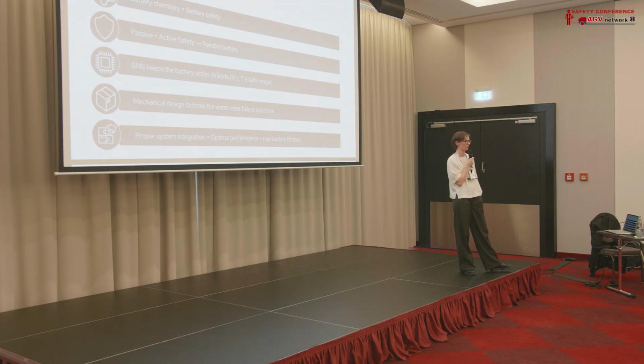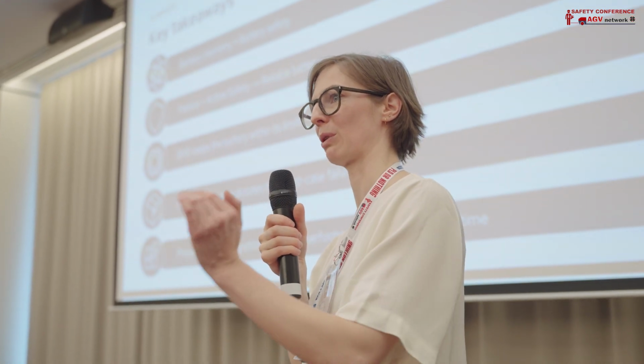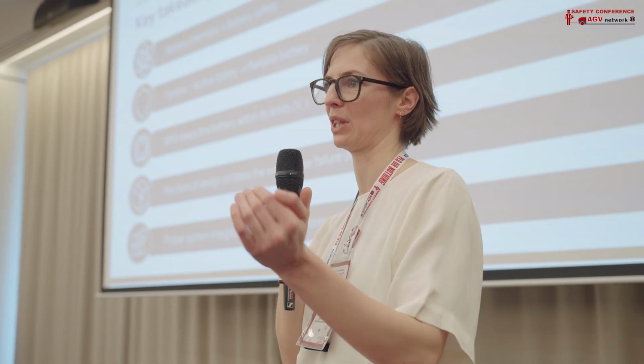We can achieve performance level D for those functions. We start with our safety concept, and our safety goals actually exceed the standards, but we always use the standards to verify that we have the correct level. Then, when we talk to our customers, we can verify and see the match between the requirements and our design. Is it common to speak of performance level for those functions in the BMS, or is it new, or is it supposed to be part of the battery standards?